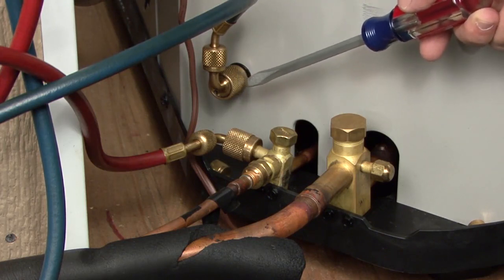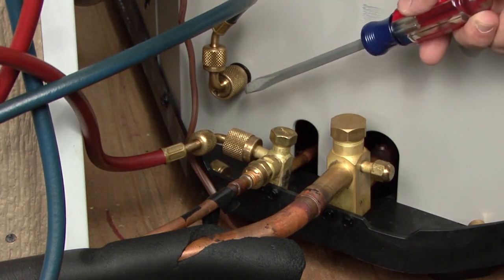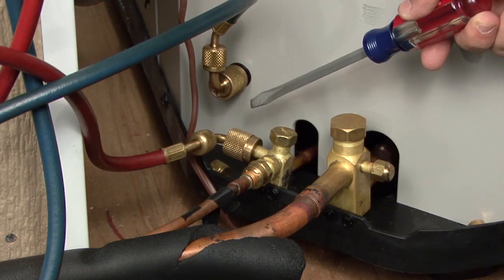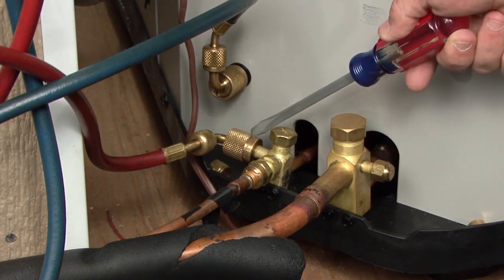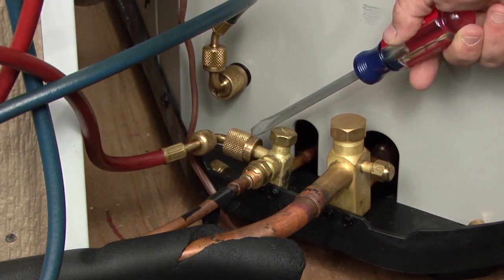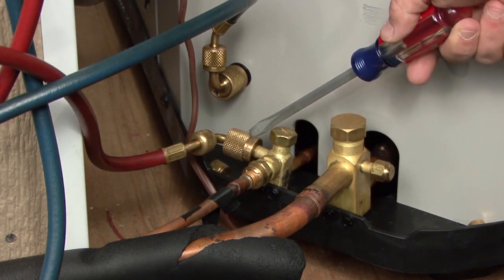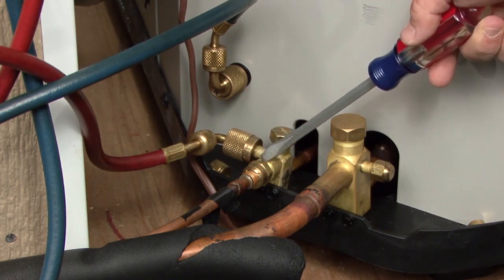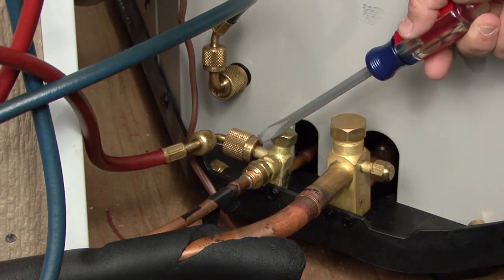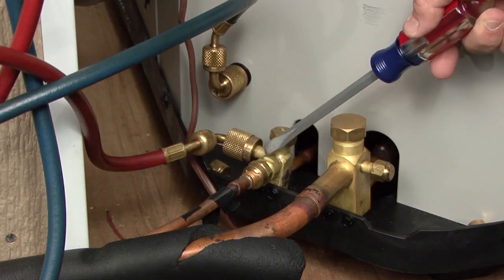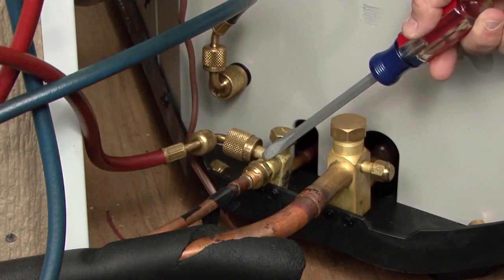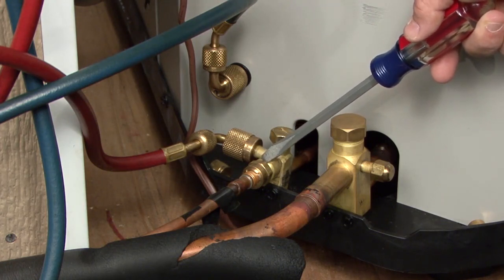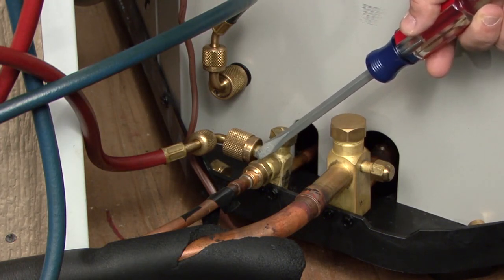So the way these gauges are set up right now, this will only read high side pressure in cooling mode. When you get in the heating mode, if you've got your high side gauge hooked here, you're not going to read head pressure because it is after your orifice. So it's actually low side, but it's so close to that orifice, it's not even really a good low side reading.